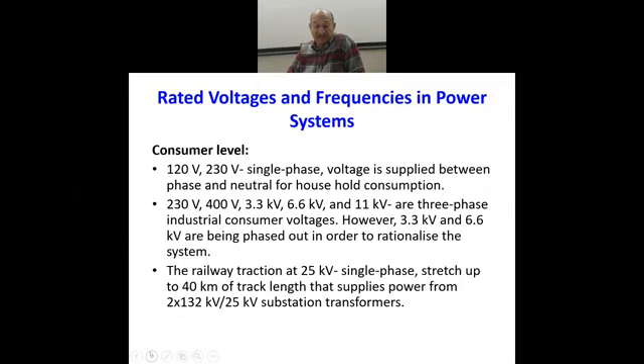And these voltage levels have slowly been phased out, because you can imagine the power handling capability depends upon the total, the power handling capability is proportional to the square of the voltage. So a 3.3 kV system and an 11 kV or 6.6 kV system would handle very little power, and the load is continuously increasing.